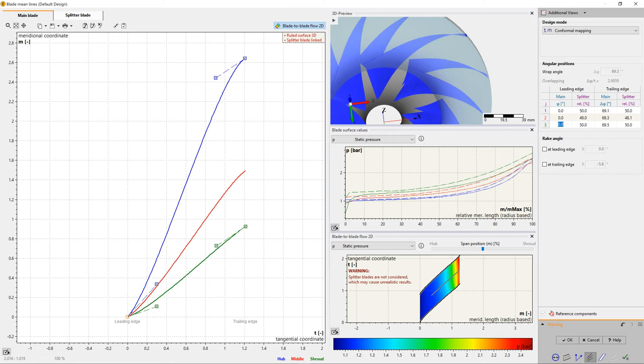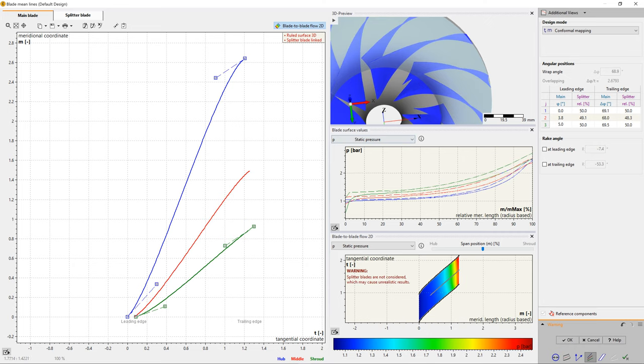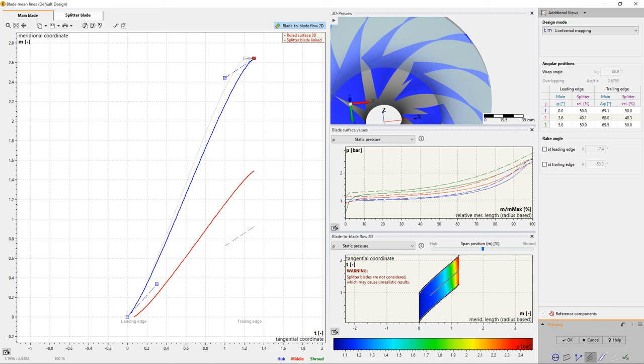The blade angles of leading and trailing edges are fixed in this design step. There are graphical and numerical possibilities to modify the wrap angle of the blade, which has a strong influence on the blade angle distribution.